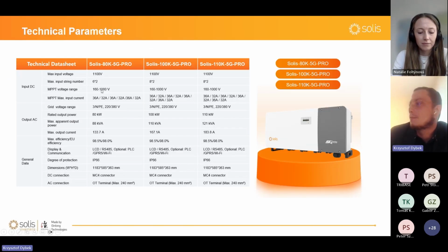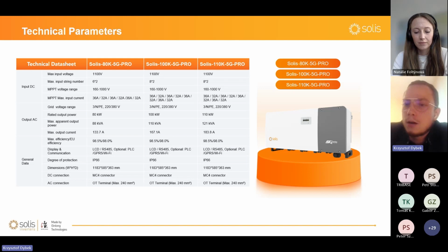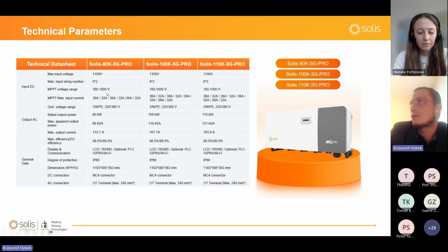And about technical parameters. So basic parameters are written there. The inverter works with 400 volts on the AC, 1100 volts input voltage per MPPT, and it has an operation range of 160 up to 1000 volts. As I said before, this should be a little bit lower than 1100 so as not to exceed this value of the MC4 connectors. 32 and 36 amps per MPPT, 2 strings per MPPT. This is also important. So you have 18 or 16 amps per string.